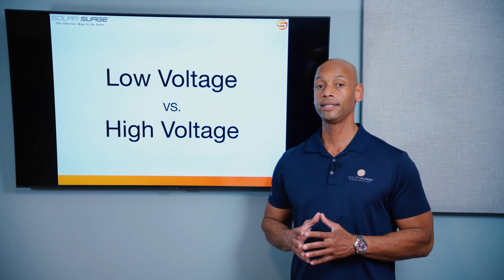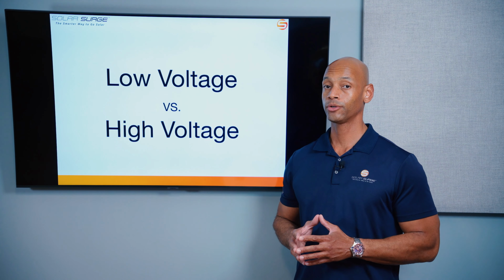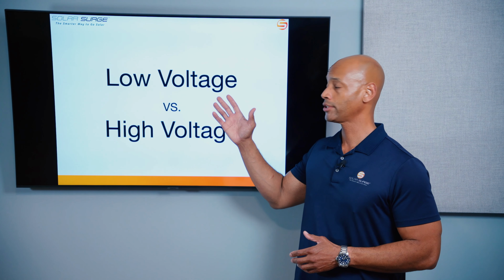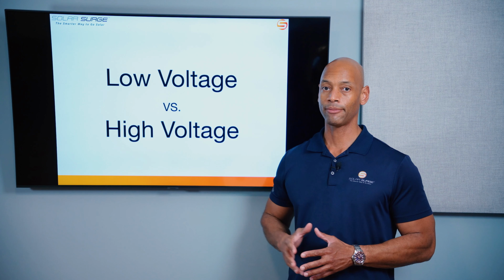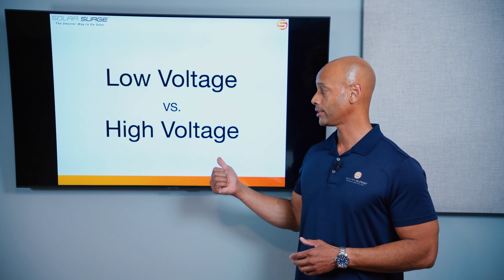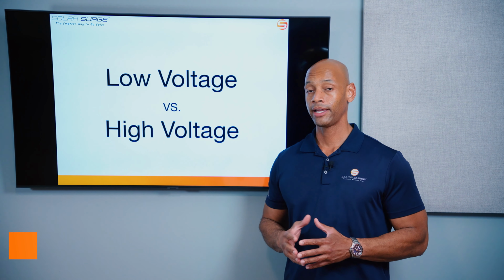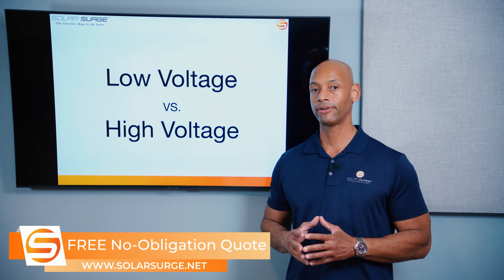When we talk about DC coupled batteries, they also fall into one of two categories: either low voltage, which is typically a 48 volt nominal voltage, or high voltage. Most solar arrays are actually wired for high voltage, somewhere in the range of 300 to 500 volts.